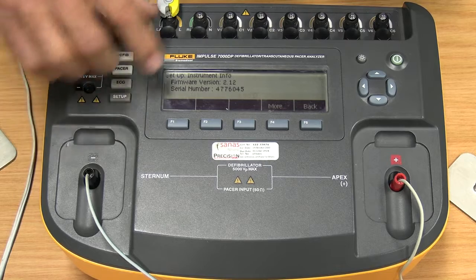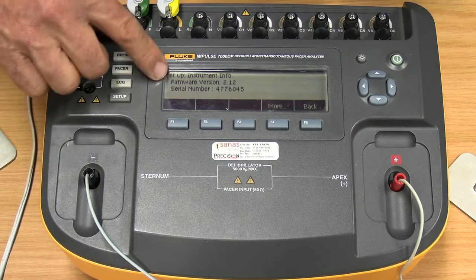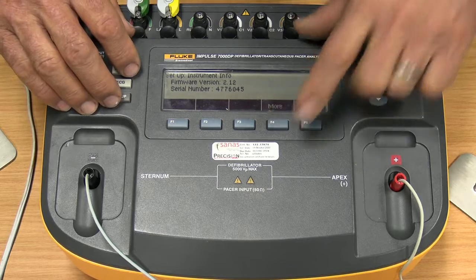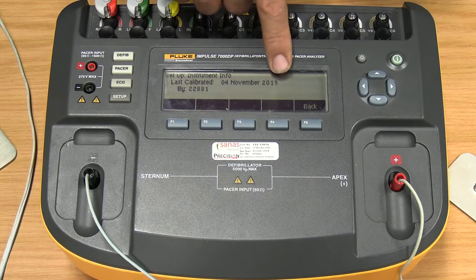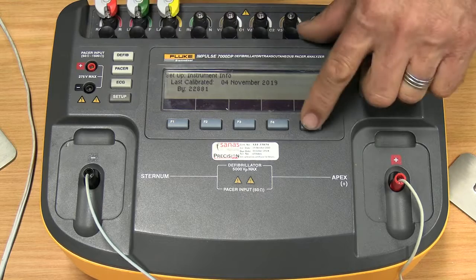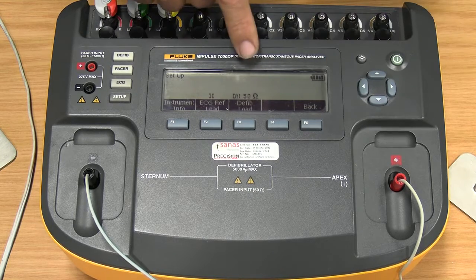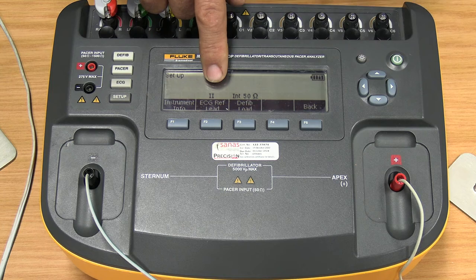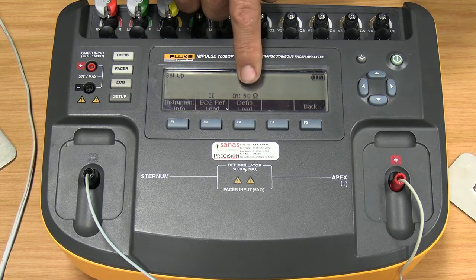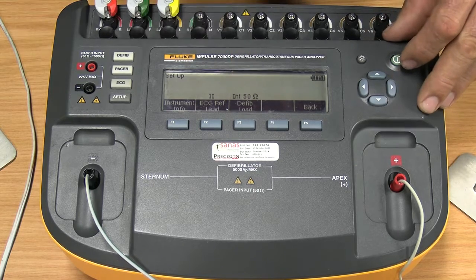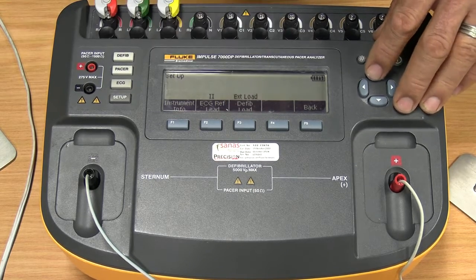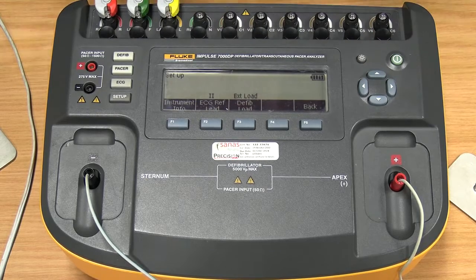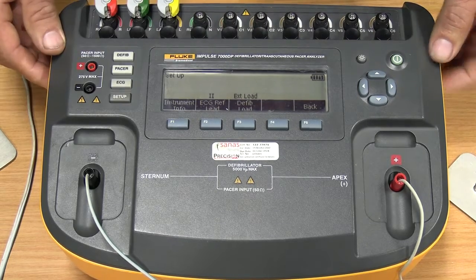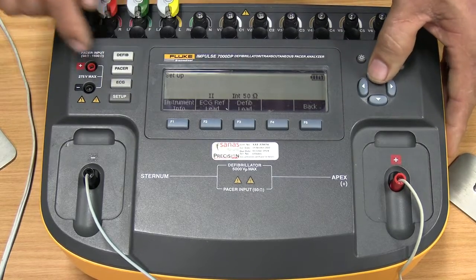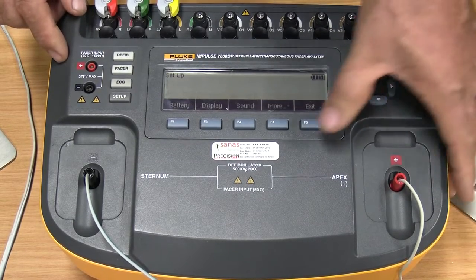Instrument info, that is just where you'll be able to see the firmware version, the serial number, and so forth of the machine. If you press the More button, that's where you'll be able to see when last it was calibrated. Go back, and then your ECG reference lead. Which lead do you want to use as reference for your synchronization measurement? And then the defib load. We always use the 50 ohm internal load, but if you've purchased the external load, which is an additional box that you purchase with the unit, you can change it to external. Let's just turn it back to internal, back, and exit.